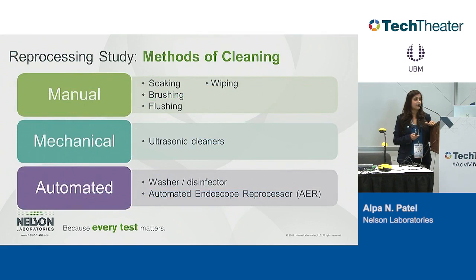Methods of cleaning, there is a manual method, there is mechanical. Of course, mechanical has been taking over, and automated is the number one way of cleaning any reusable instruments. It used to be manual, but to take the human factor out of it, we're moving towards the automated method, and washer disinfectors are predominantly used at the hospital. Although all 3 are part of the cleaning aspect for all the reusable medical devices.